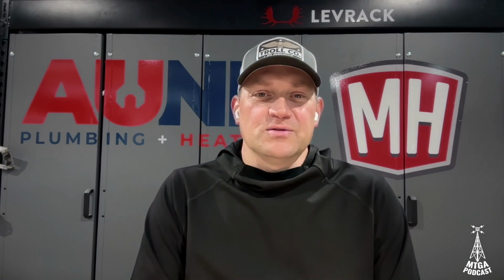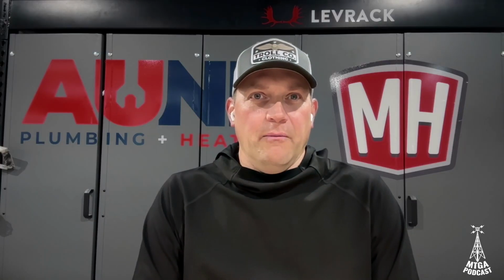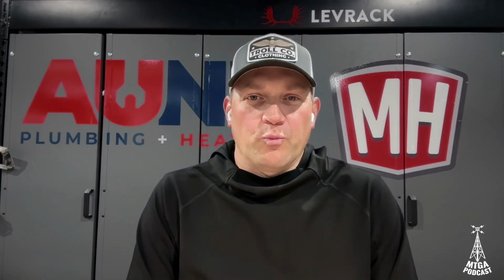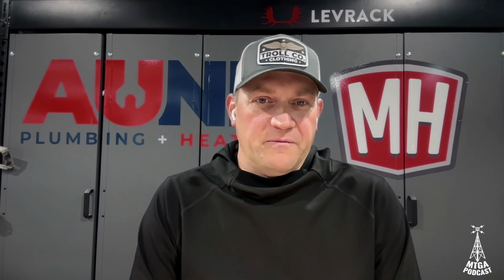Like I said, the small one's 28,000 BTUs. That's less heat capacity than a standard 50-gallon gas water heater. Absolutely. So that's an economy version indoor tank water heater. I didn't time it because we were doing other startup tasks in the process, but I would say it took 45 minutes to heat that tank, the 42 gallon.